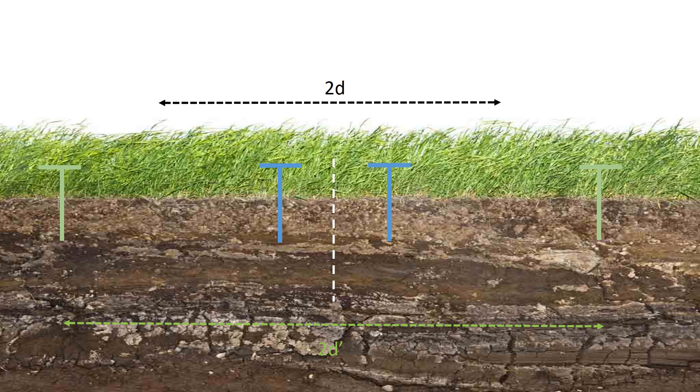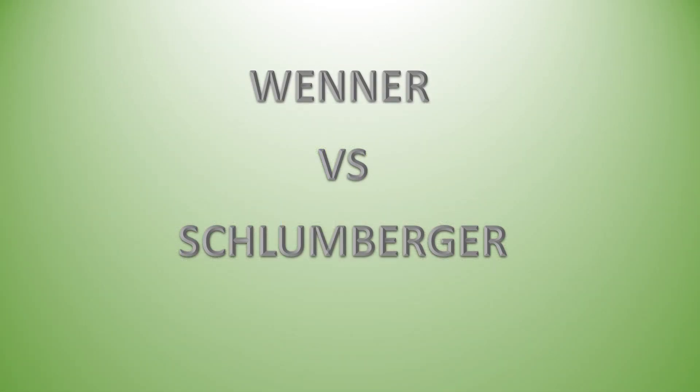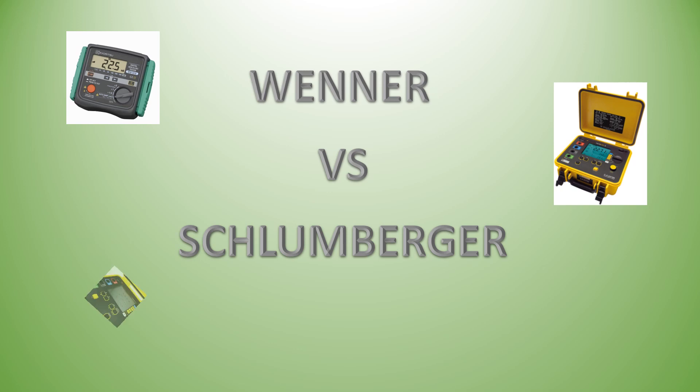Whereas all four electrodes need to be moved at the same time with the Wenner method. Although the Schlumberger method saves time, the Wenner method is better known and more widely used. The mathematical formula necessary is also much simpler. Nevertheless, many measurement instruments include both formulas for instant calculation of the resistivity values with either method.